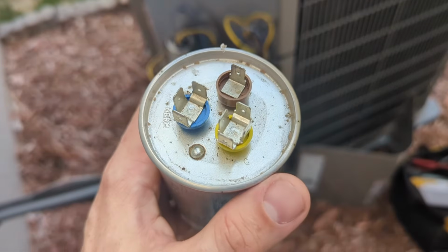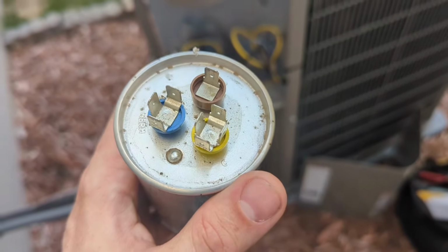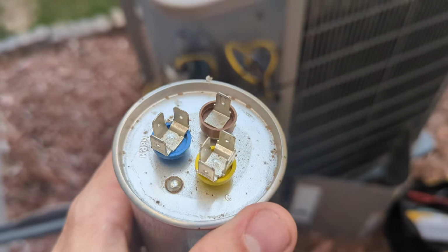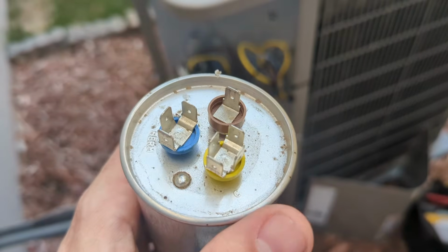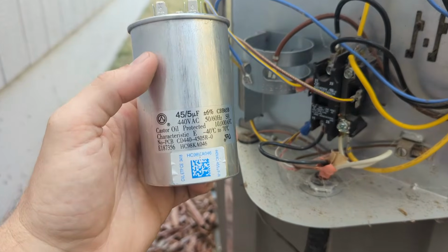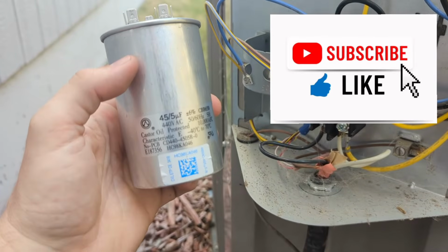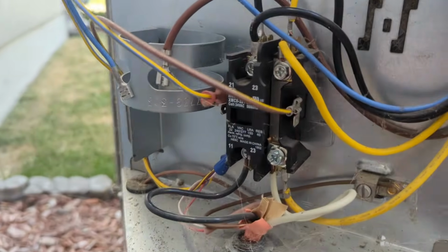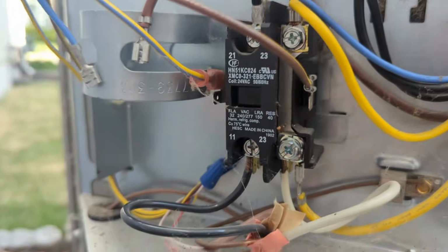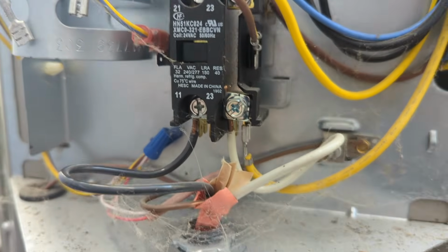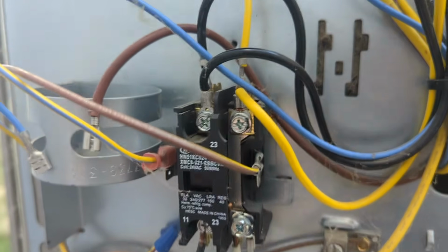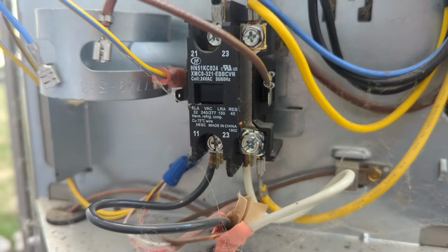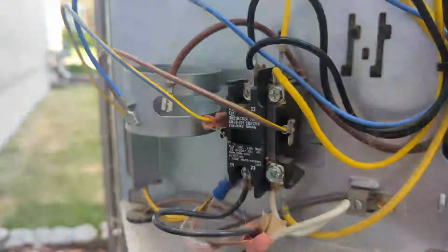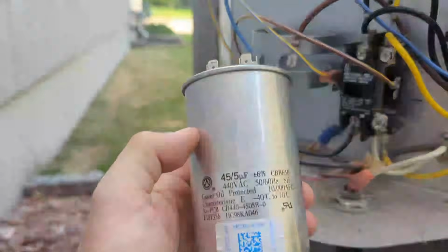Before you remove the old capacitor, take note of which wire goes to which terminal, and make sure the wires go back where they landed. So I'm going to show you what to look for and how to test it, so that you know that the capacitor is the bad part. So first thing, I looked at the contactor. This is the contactor, and it looks great. All the lines coming in, going out, everything looks clean. There's no shorts. The spring is depressed, so that's good. It's passing power through.